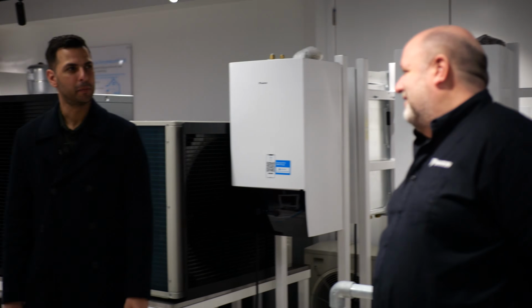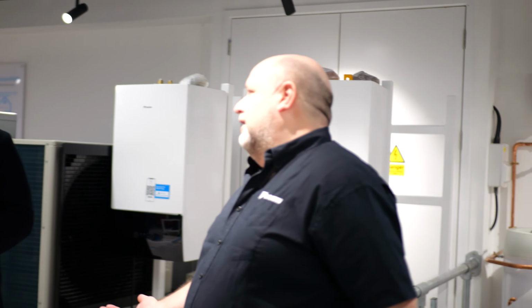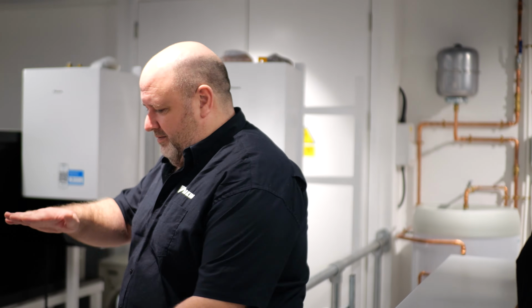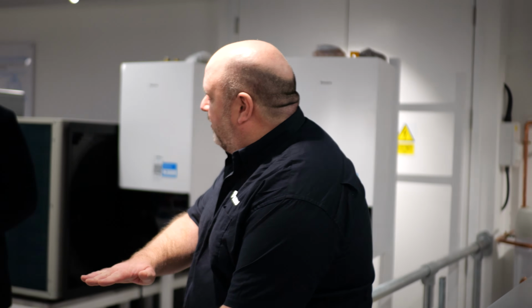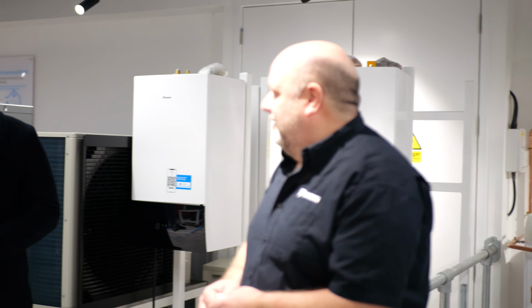Wouldn't the compressor run at high speed because it's undersized? No, we're talking about higher ambient conditions, higher ambient, less capacity. So where you want less capacity - as you rightly said, the size 5 is more energy efficient. It's a smaller compressor, so you've got that range being much lower compared to the size 8 being a bit higher. This is where you gain on these heat pumps, is actually the lower range of the capacity of the heat pump.